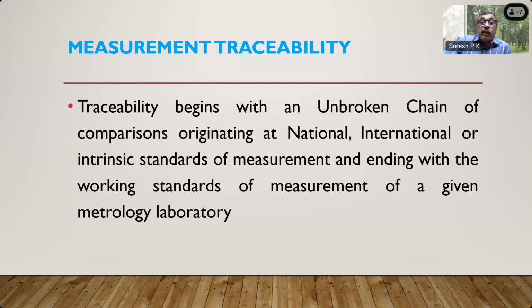So that is the traceability chain. Traceability starts with the international standard. It comes to the national standard, in our case, the National Physical Laboratory (NPL). Then it goes to working standards. Then it goes to measuring instruments. Probably you can say in our case NPL, RRSL, or laboratories like FCRI, and then you can say working standards of other industries, and then from there, working standard to the measurement instrument.